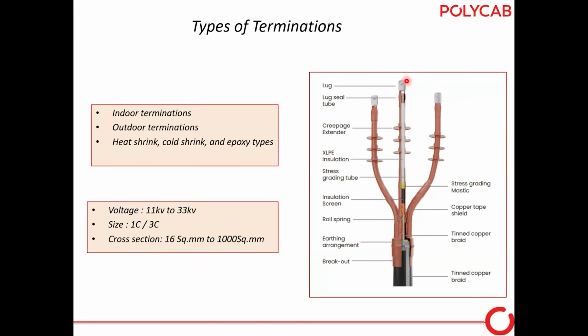Sorry. Over the lug, seal tubes are there. Over that, insulating tubes come. These creepage extenders we use for the extension of creepage, or sometimes people say the rain shed. This is the insulation screen. Then this is the breakout and earthing arrangement we do. So overall, this is the outdoor termination.